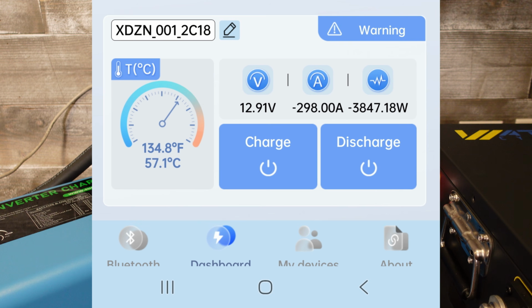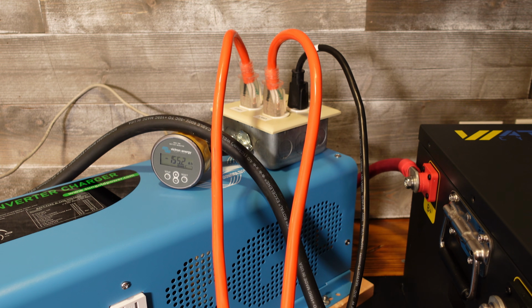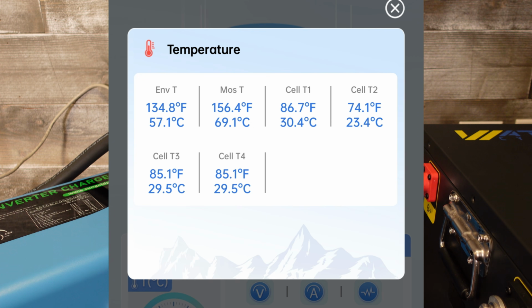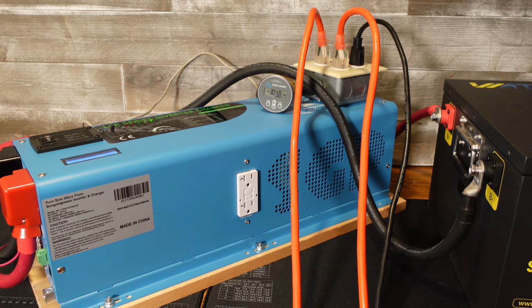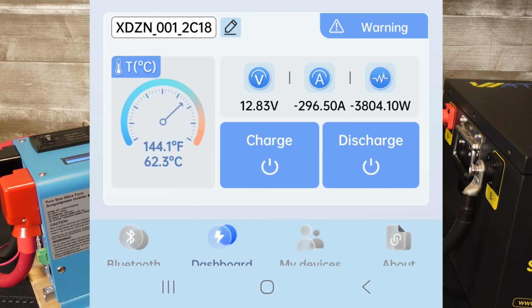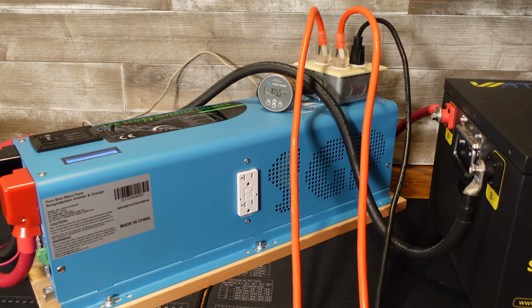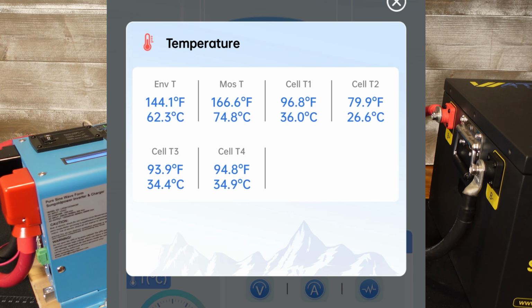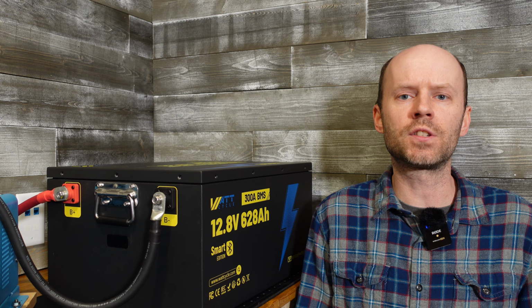All right, we're 30 minutes in, we're at 298 amps. 155 amp hours discharged so far. Our temperatures are sitting at 156 degrees on the MOSFET temperature sensor and 134 degrees on the environmental temperature sensor. 1 hour and 1 minute, we're at 296 amps. 305 amp hours discharged so far, and the temperatures are reading 166 on the MOSFETs and 144 on the ENV sensor. And the test finished successfully.